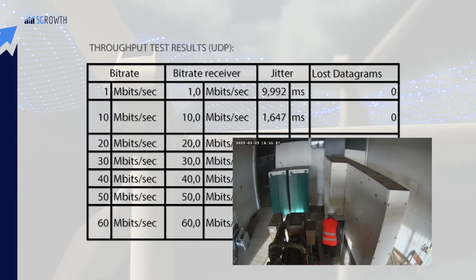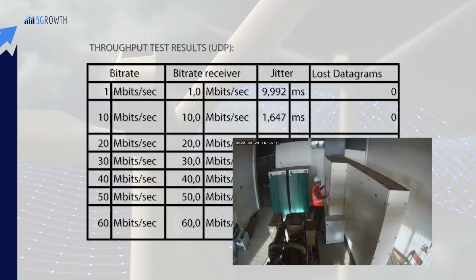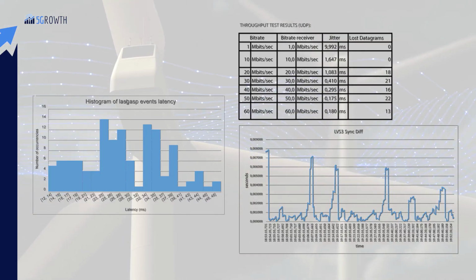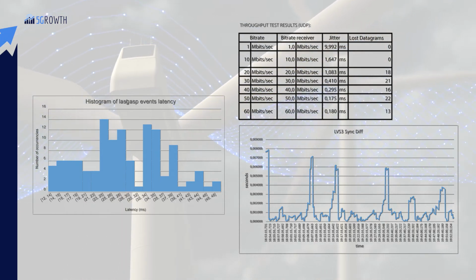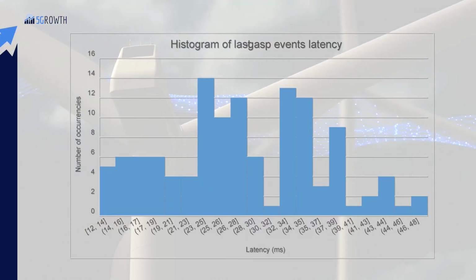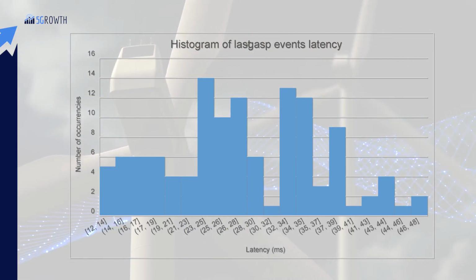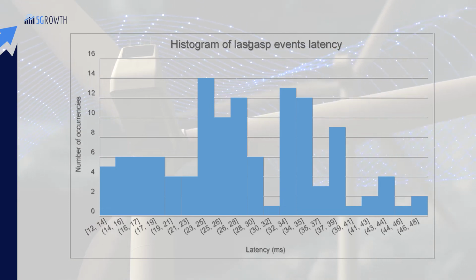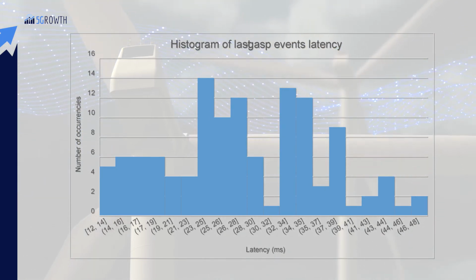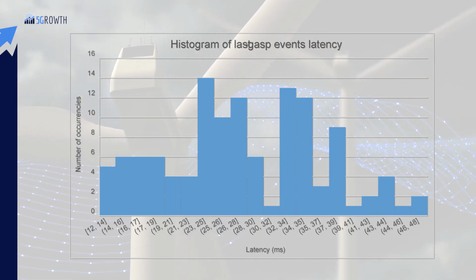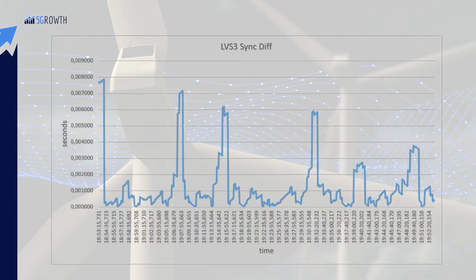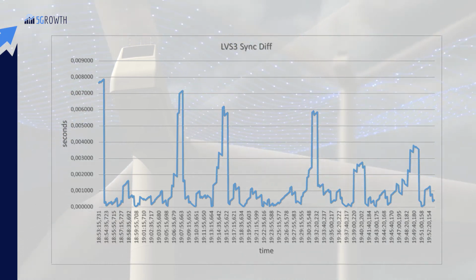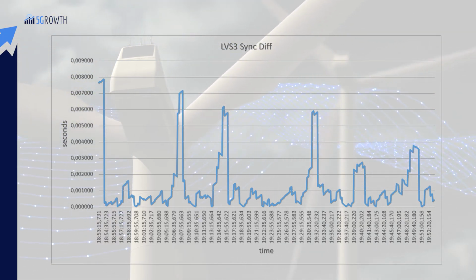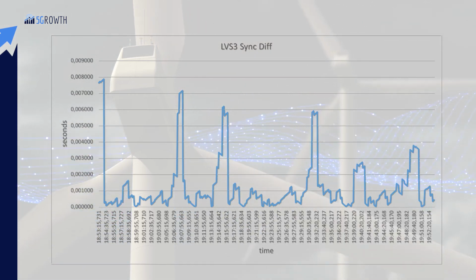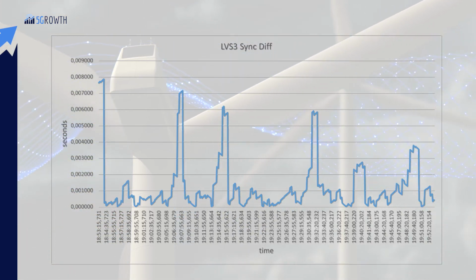During the test period, the service availability was 100% and no packet loss was detected up to 10 megabits per second. The data rate uplink could reach 60 megabits per second. The most relevant core KPI on latency was measured in use case 2. The last gasp information, end-to-end latency between the low-voltage sensors LVS3 installed in the low-voltage network and the G-Smart installed in the secondary substation was measured directly in the application, which was 27.94 milliseconds on average. The latency in the time synchronization service between the LVS3 device and the NTP server was 13.4 milliseconds average, achieving an average difference of 1.21 milliseconds between LVS3 devices when comparing each one's synchronized time.